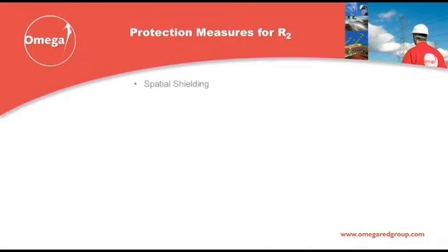Some of the measures that can be used to reduce or mitigate the effects of LEMP and consequently reduce the R2 risk of loss of service to the public will already be in place by virtue of the building fabric or the nature of the building services. The LEMP effect will be attenuated somewhat if the structure has a steel, reinforced concrete or other conductive frame, and this frame is earthed.